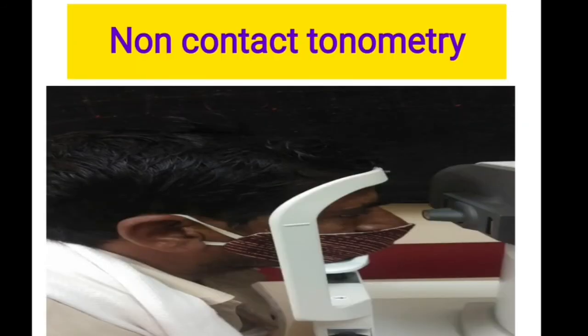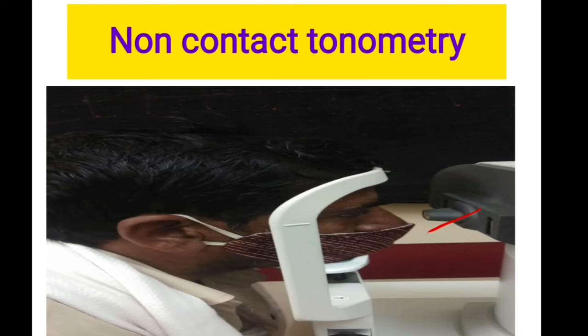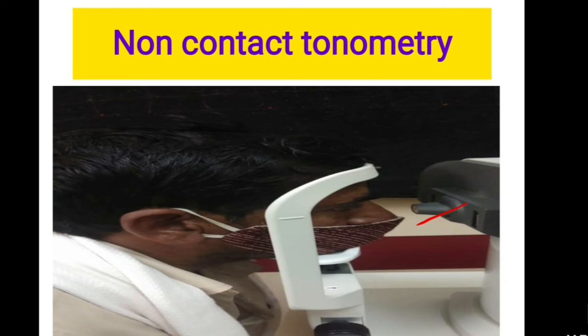Non-contact tonometry (NCT): the patient positions their chin and head against the instrument. An air puff is produced from the machine, which deforms the cornea. The machine measures the time or force of the air puff required to create a standard amount of corneal deformation. It is based on the principle of applanation tonometry. Main advantage: used for screening because it is fast and requires no anesthetic agent. Disadvantages: in eyes with very high or very low IOP, readings may not be accurate.